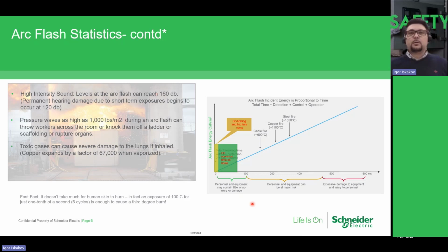A typical protection relay works in 30 to 35 milliseconds at the fastest overcurrent stage, but arc flash protection can do it in less than 10 milliseconds. Our new arc flash protection devices like A1 and A3 are able to send a signal from the detecting stage to the closing contact for the command on the circuit breaker in 2 milliseconds or even less, with two high-speed outputs. For some cases, like circuit breaker protection, we can use additional contacts with a 9 millisecond tripping time. We are very fast in detecting the arc flash and sending the command to the circuit breaker. It's almost instantaneous.